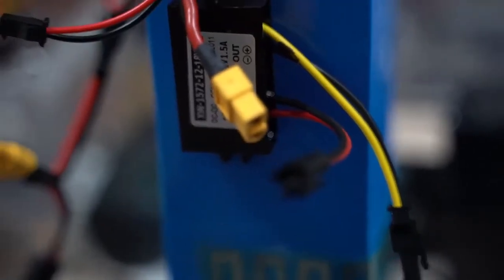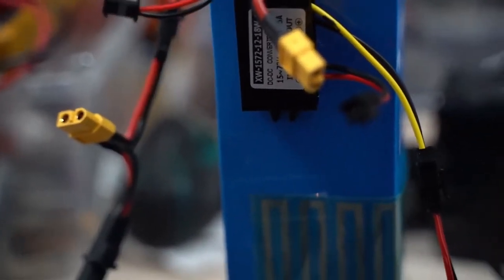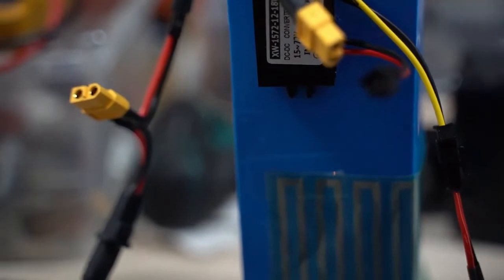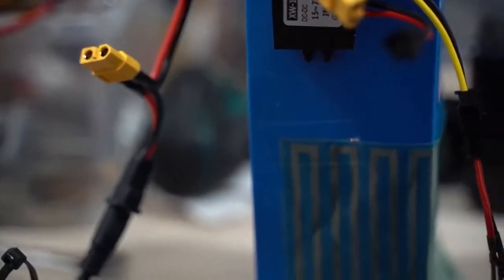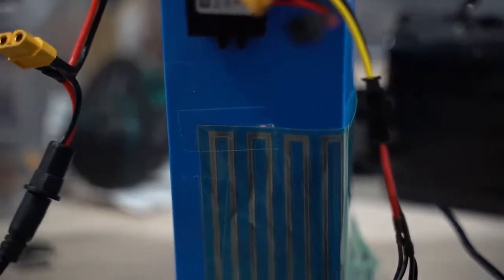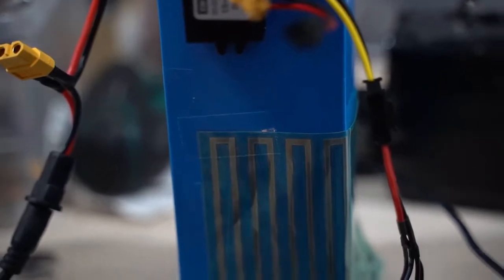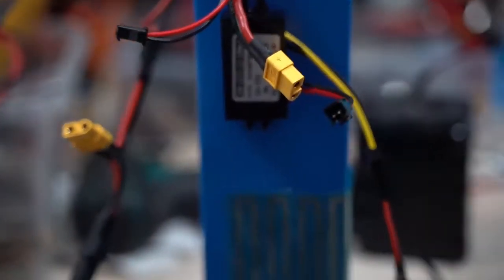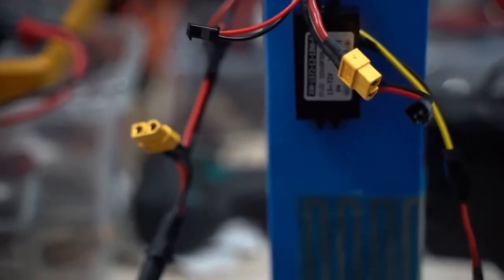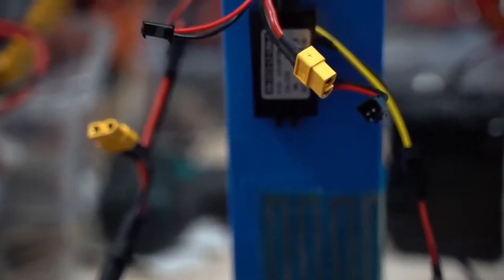Okay, so there's something interesting I want to point out. As with discharging a sub-zero battery, where the discharge just falls off the cliff, or it discharges very rapidly, the same can be said of charging. So the charging curve for a very cold battery, close to 0 or sub-zero, is that the battery is going to charge up to a suboptimal upper limit.